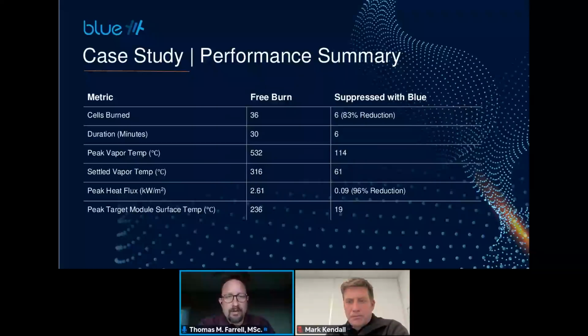During the free burn, the module above got up to about 236 degrees surface temperature, directly above the battery. So the module above, if it had been populated with lithium-ion battery cells, almost certainly would have gone into thermal runaway at that level. Whereas if we take that exact same system with blue, it got up to 19 degrees, about a 7-degree rise.